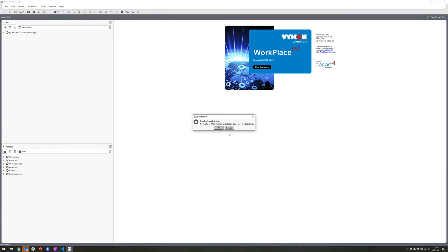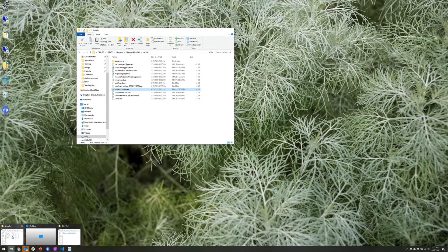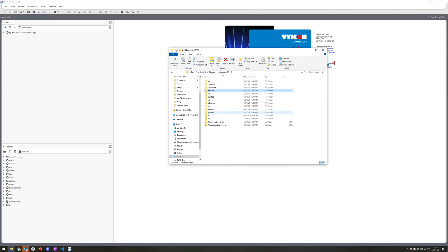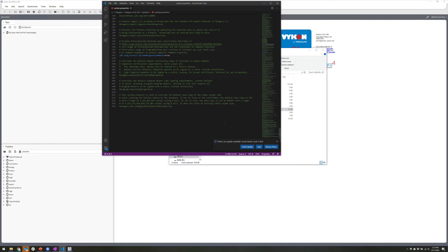This is an error message you probably haven't seen before. It says it couldn't validate the certificate chain for this specific module, and before I can even put the code into a station, the workbench is going to say I can't open it at all. I'm going to hit OK, and now we're going to go into that system.properties file, which is in my install directory under defaults. You'll see the system.properties file, and I can open it up in my text editor.